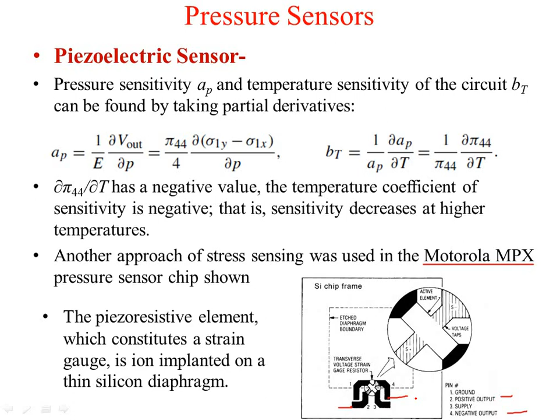So the excitation current is passed through the longitudinal resistors tap 1 and 3, and you will be getting the output across 2 and 4. So the stress establishes the transverse electric field in the resistors that is sensed by the voltage tap 2 and 4. So the thin diaphragm with 1 mm square area size may be formed by using one of the commonly used silicon etching solutions.